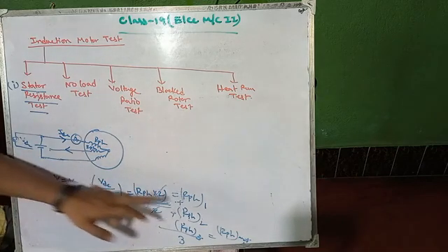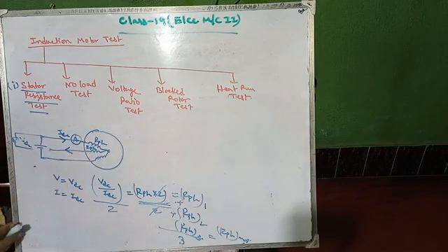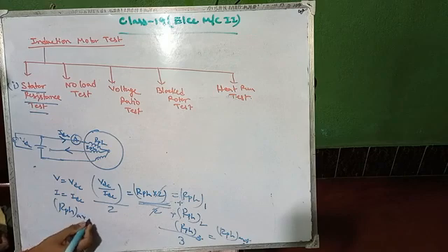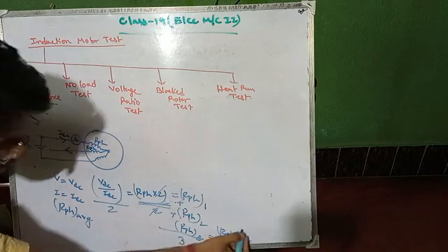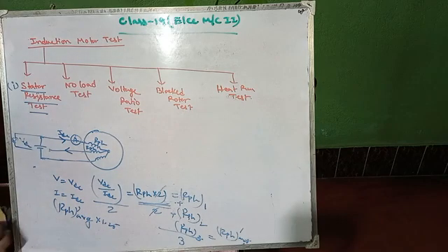But always remember, this value is for DC. We know that for AC the resistance is higher than the DC value. So we multiply RPH average, call it RPH average dash, by 1.25 to get the actual resistance per phase for AC.